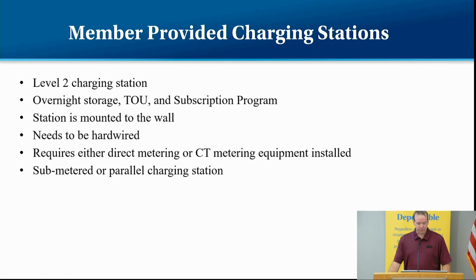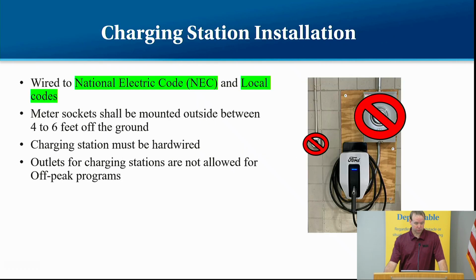Member-provided charging stations, again, need to be level 2 wall mounted. They can work with any of our programs, the overnight, the time of use, or the subscription. They need to be mounted to the wall and hardwired, and can either be direct metered, CT metered, sub-metered, or parallel, depending upon the installation needs. They need to be wired to the National Electric Code and local codes. The meters shall be mounted outside between 4 to 6 feet off the ground. This picture shows an installation where the meter was mounted inside right next to the charger. That's a no-go. The meter needs to be outside so that we have access to it.